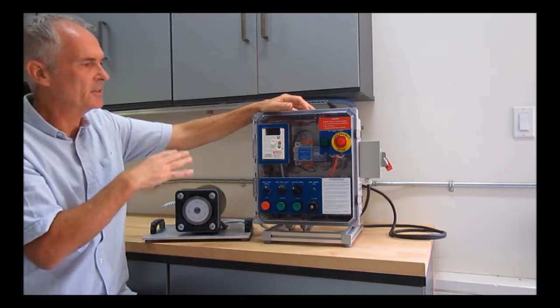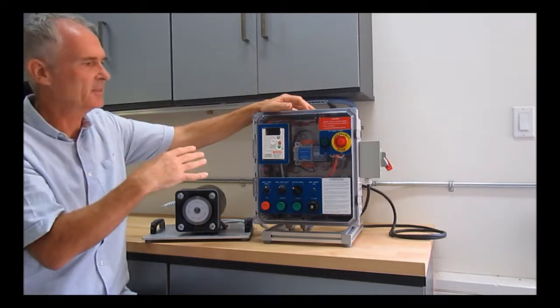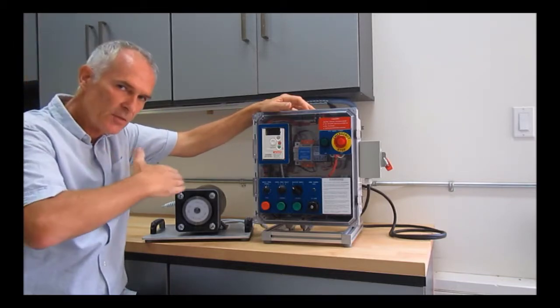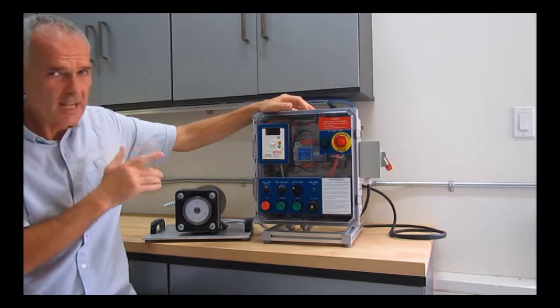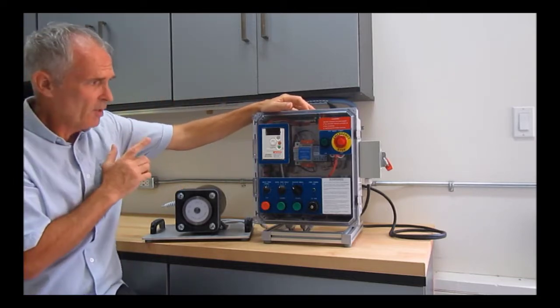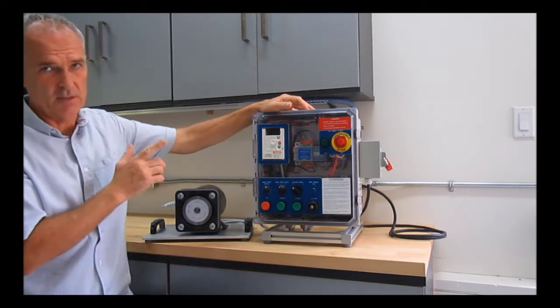The other type of control is what's called standard mode or scalar mode. A lot of you may be familiar with the term volts per hertz. It uses that volts per hertz ratio - it scales the voltage to the frequency of the motor and uses it through the operating range of the motor.